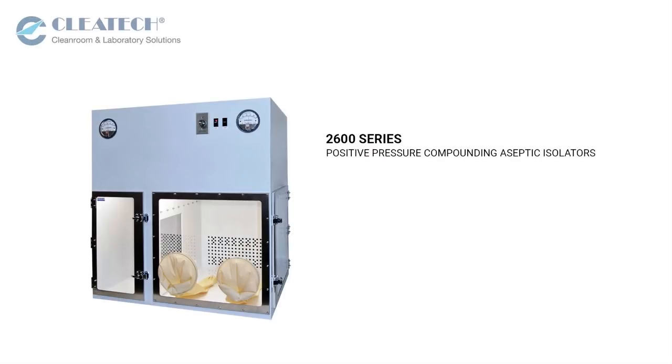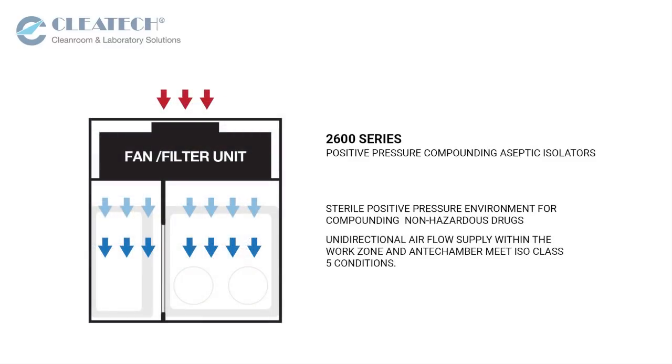The 2600 series positive pressure compounding aseptic isolators are designed to provide a sterile positive pressure environment for compounding non-hazardous drugs. The HEPA-filtered unidirectional airflow supply within the work zone and antechamber meet ISO class 5 conditions.